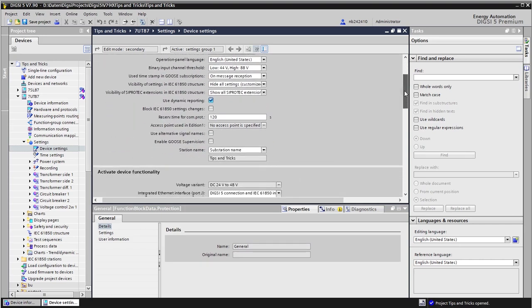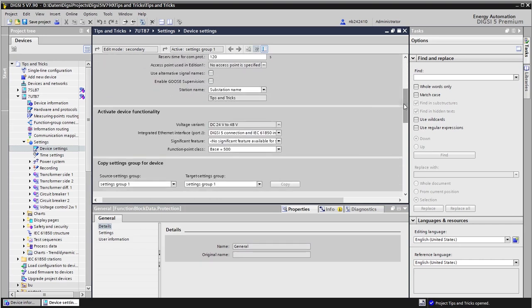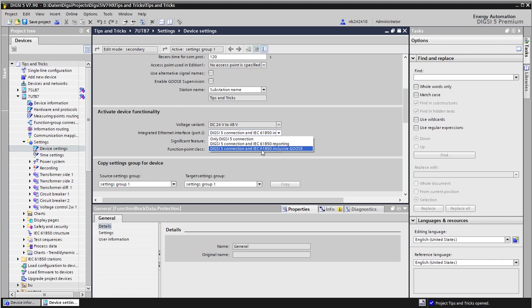Further down, under activate device functionality, if you use the port J as we do here, then ensure that you select inclusive GOOSE, otherwise it will not work.